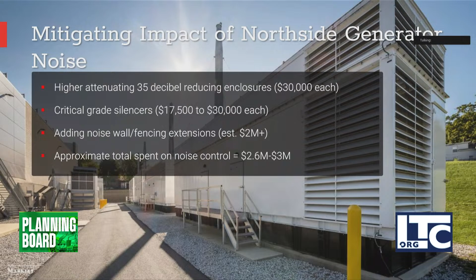So this cooling tower is going to be put on the eastern side of the property. Markley's looking at acoustical silencers to reduce noise from the fan discharges. They're also looking at panels to be installed to reduce noise from the air intakes to the cooling towers. And additionally, they'll be looking at installing an improved sound wall on the property line on the eastern side to reduce noise from the cooling towers. Can you go back one slide, please? So you can see the cost of each mitigation measure for each modular cooling tower. So we think Markley's spending a great deal of money to control air quality and noise for generators that run such a short amount of time in general, on average.